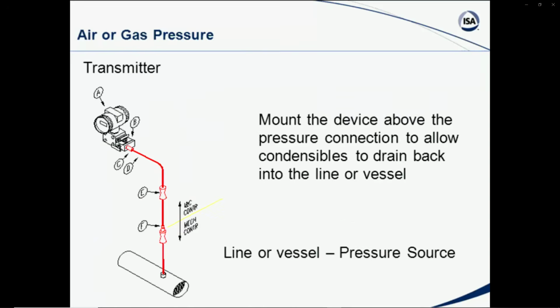Conversely, on an air or gas situation, we show this one here, the transmitter is located above the particular connection point to the process, either a line or a vessel, and the condensables will drain back down into the tank. So this would be a way of installing a transmitter, a pressure device, if you will, on an air or gas situation. So you could have questions dealing with how to install a particular device with respect to the kind of fluid that you're measuring.